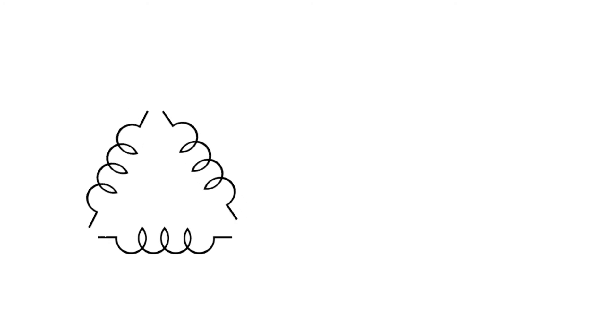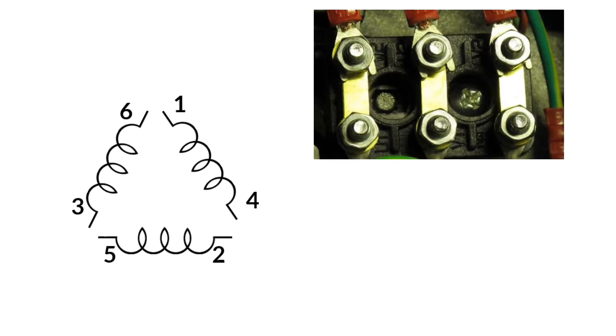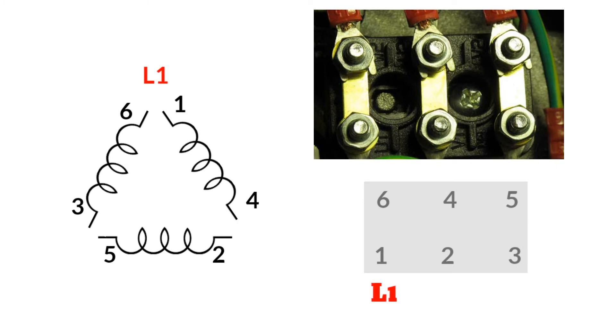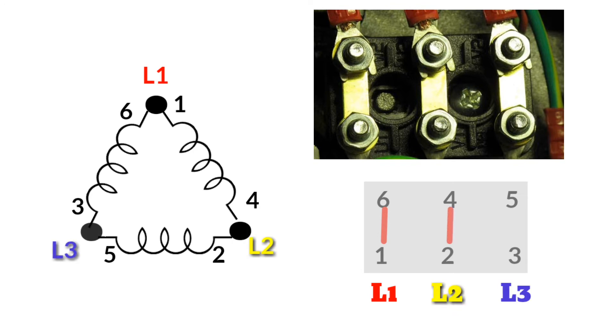In delta connection, the opposite ends of 3 coils are connected together. In other words, the end of each coil is connected with the starting point of another coil, and 3 wires are taken out from the coil joints. There is no neutral or star point connected in delta connection. To make a delta connection: line 1, connect number 1 terminal to number 6 terminal; line 2, connect number 2 terminal to number 4 terminal; line 3, connect number 3 terminal to number 5 terminal.